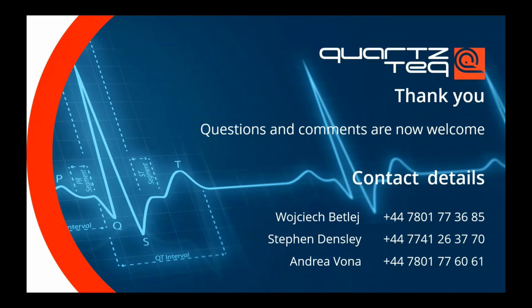Okay, thank you, Wojciech. We have one more question that's just arrived. Do we have any experience with the cause of circulating currents through the damper fingers and wedges that have produced electrical erosion even in retaining rings? Oh yes, it's a good question. I'm really happy to hear that, because over the years we had a chance to work with customers who had machines experiencing these particular problems. We know that the damage caused by these circulating currents can be extremely extensive.